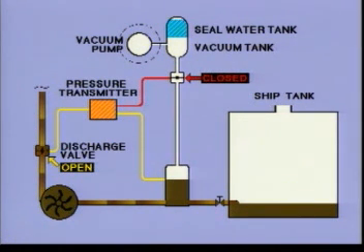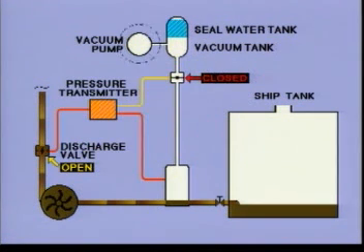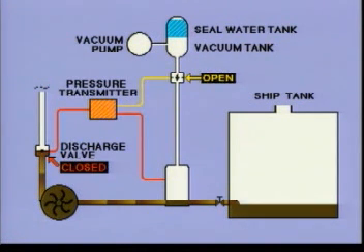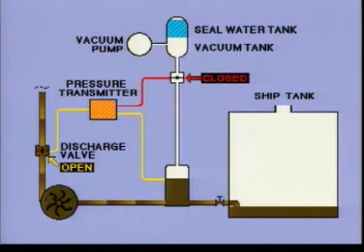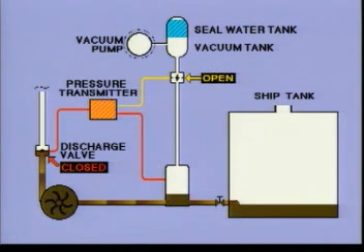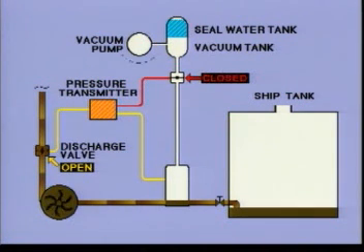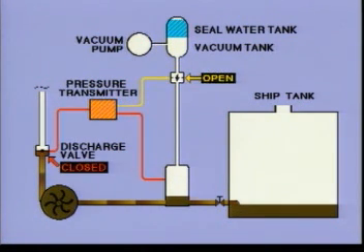The pump starts to work in a priming cycle. The pump fills and empties regularly. Watch the priming cycle. The tank is empty when the pressure at the pressure side of the pump remains at 0 and the discharge valve doesn't open anymore. Close the valve to the tank and stop the pump.